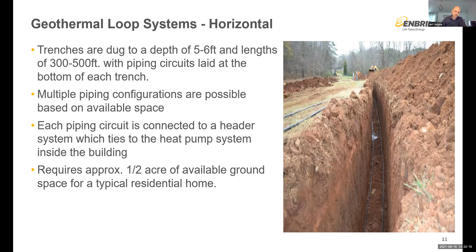These systems are flexible. They can even be installed to provide energy for entire communities. There's a number of different ways to do that. Network geothermal systems have seen a lot of press lately and a lot of interest, especially down in the northern United States. There's a number of projects going in, as well as in Austin, Texas. Whisper Valley is one of the largest. They basically leverage an ambient loop type application. So there are individual heat pumps in each building that provide the final tempered energy required for the thermal conditioning of that building. And there's one single interconnected ambient loop that runs throughout the property or throughout the community if it's a community-based system. So that heat exchanger system is connected to each individual building.